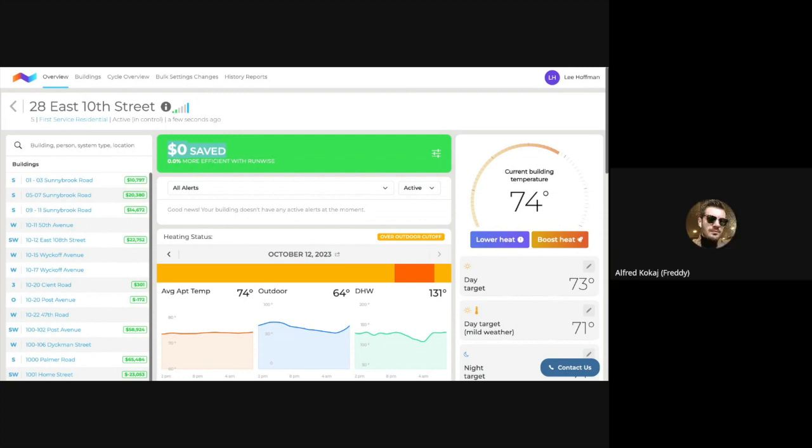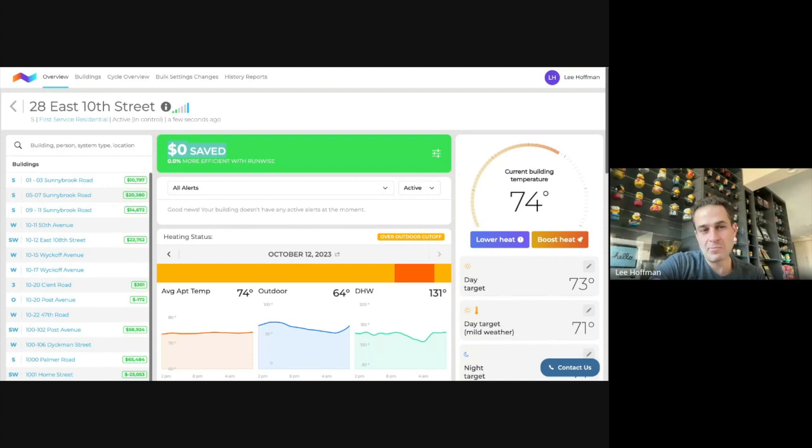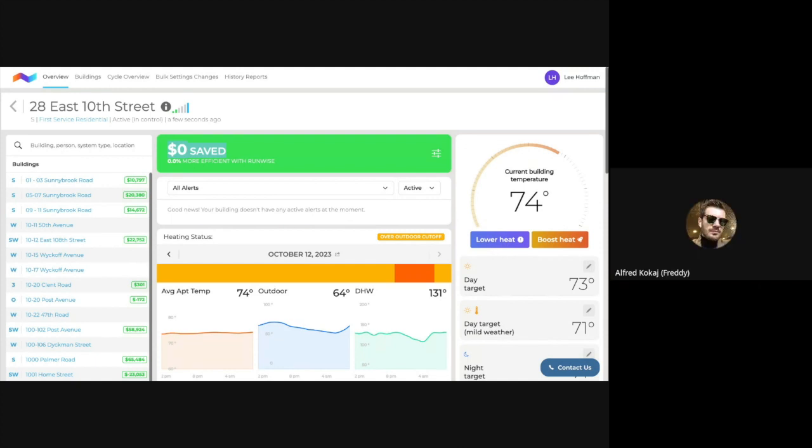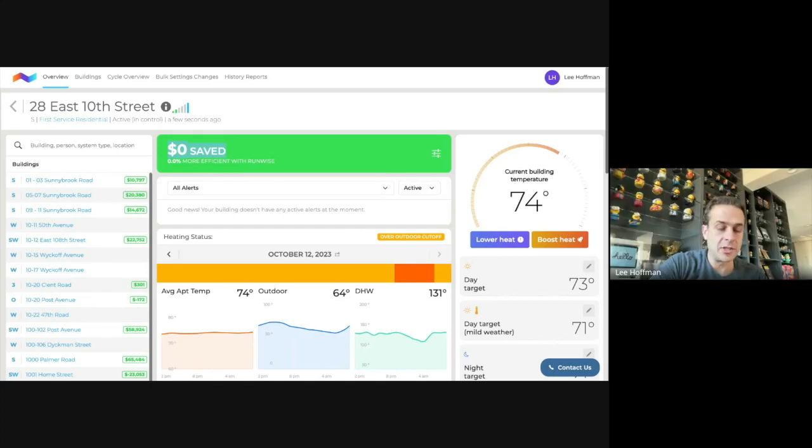Lee, I got a question. Yes. What is the normal water loss on the line per unit, or I can give you any of the building sizes that I have? A good reference is 1 gallon per unit. Below 1 gallon per unit is where you want to be.